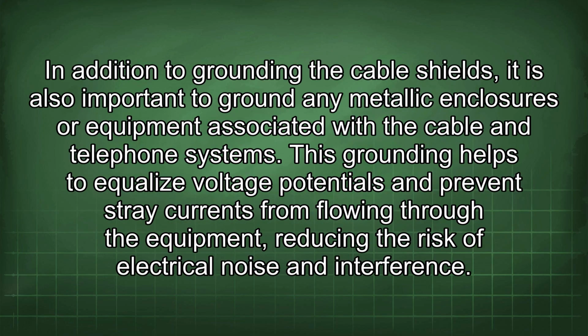In addition to grounding the cable shields, it is also important to ground any metallic enclosures or equipment associated with the cable and telephone systems.